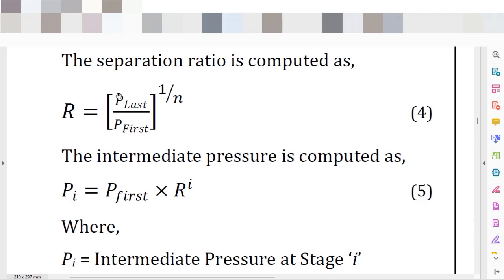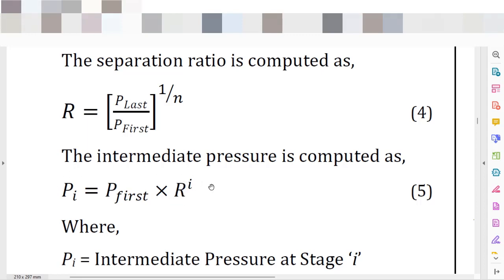Once you have calculated the global pressure ratio, to find the interstage pressure ratio you apply the equation: the global pressure ratio raised to the power of one divided by the number of stages gives you the interstage pressure ratio. With this result, you can define the discharge pressure of each stage. For instance, the inlet pressure multiplied by the pressure ratio gives you the discharge pressure of the first stage. The discharge pressure of the first stage multiplied by the pressure ratio gives you the discharge pressure of the second stage.